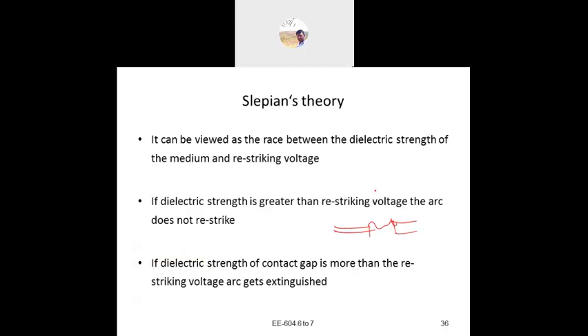Suppose air is the dielectric medium. If the dielectric strength of the air is greater than the restriking voltage, the arc does not restrike, so the arc will be quenched. But if the restriking voltage is greater than the dielectric strength, then the arc is not extinguished, and at that time the arc continuously flows.